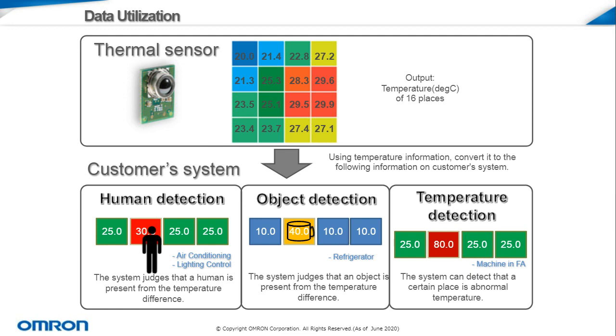Lastly, the sensor can be used to detect abnormalities in general temperature applications. This includes several machines in factory automation or industrial applications. For example, the sensor can be used in power distribution panels to monitor temperature spikes on certain components, which may alert to potential malfunctions in the hardware. The single pixel option is very useful here — close-quartered and measuring the temperature of certain objects like wiring or couplings to make sure they're not overheating and alert the user if a catastrophic situation may arise.